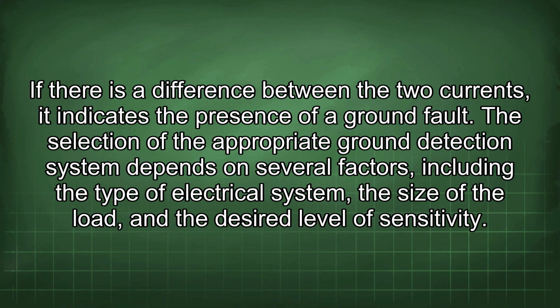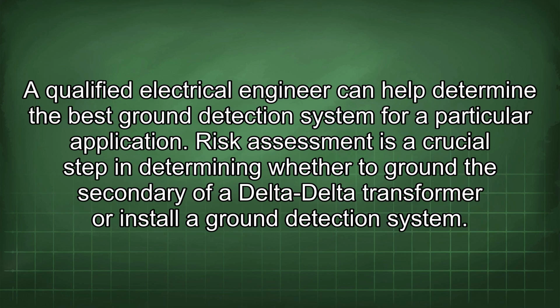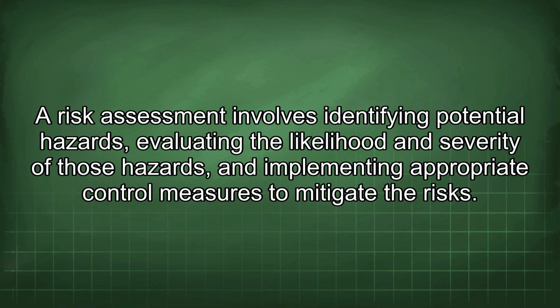The selection of the appropriate ground detection system depends on several factors, including the type of electrical system, the size of the load, and the desired level of sensitivity. A qualified electrical engineer can help determine the best ground detection system for a particular application. Risk assessment is a crucial step in determining whether to ground the secondary of a delta-delta transformer or install a ground detection system. A risk assessment involves identifying potential hazards, evaluating the likelihood and severity of those hazards, and implementing appropriate control measures to mitigate the risks.